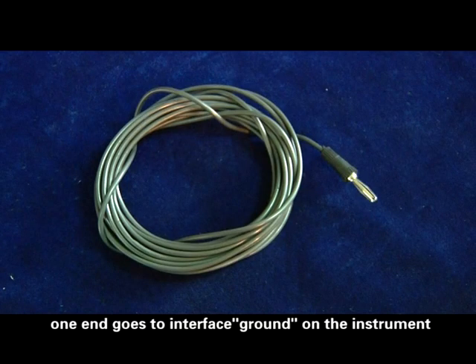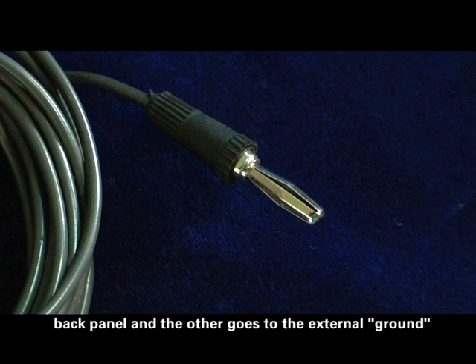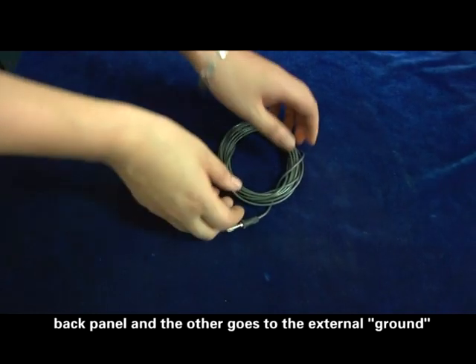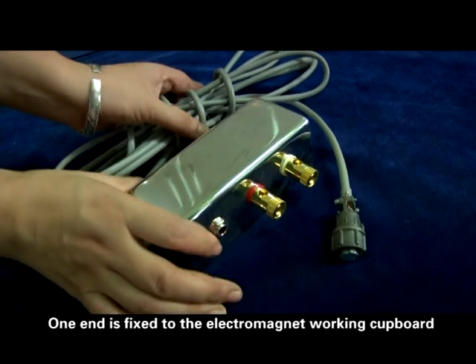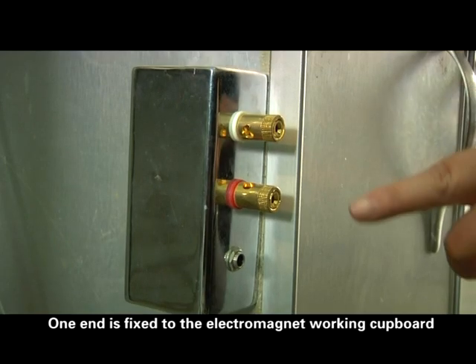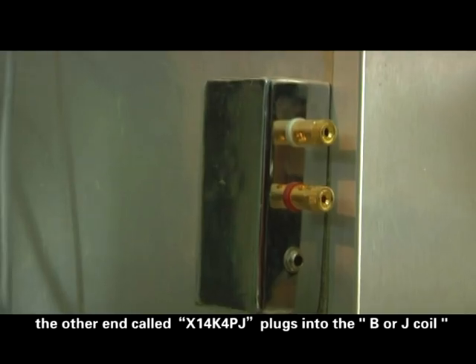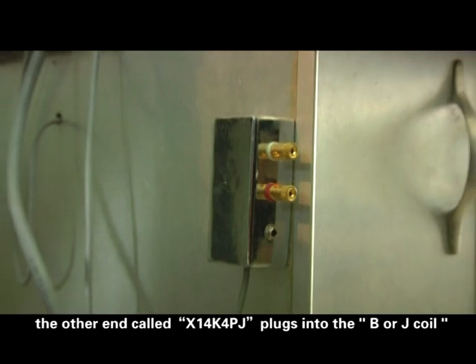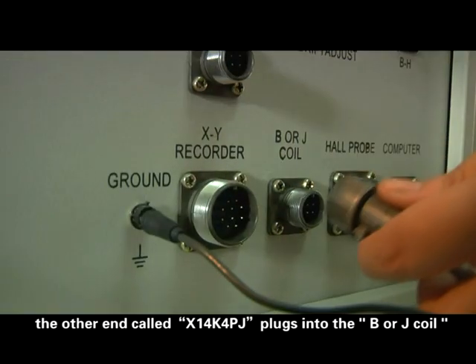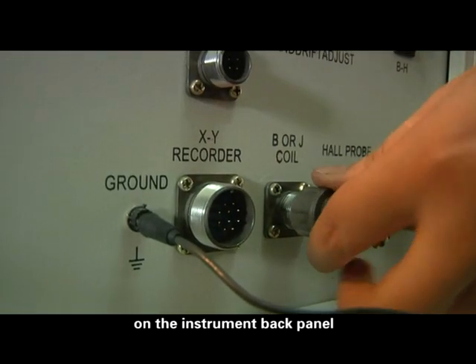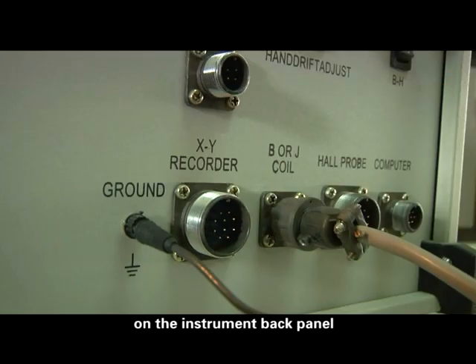Ground line. One end goes to interface ground on the instrument back panel, and the other goes to the external ground. B or J coil box. One end is fixed to the electromagnet working cupboard. The other end, called X14K4PJ, plugs into the B or J coil on the instrument back panel.